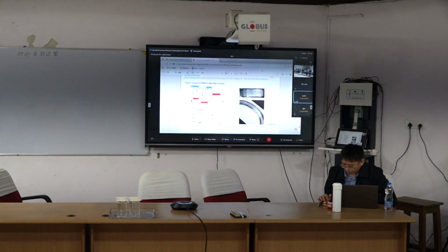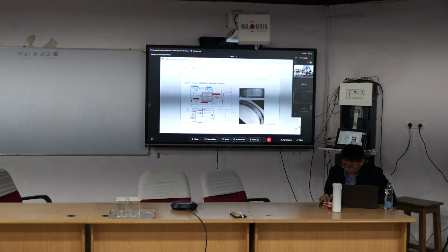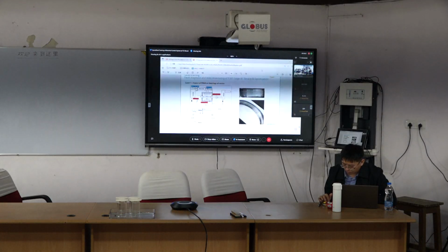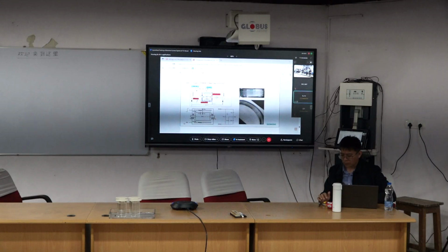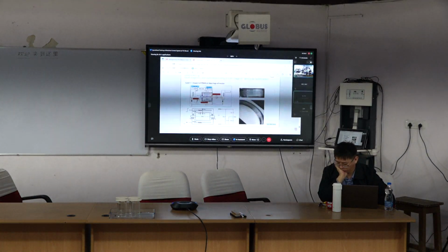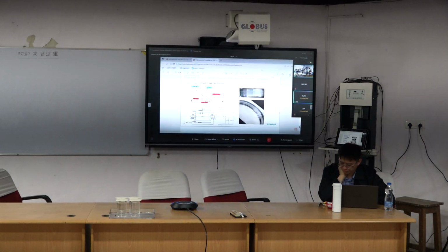In the same way, the motor cable capacitance changes polarity with every switching edge at the inverter output. The polarity of the capacitance CWH, this one, between the winding and housing, is also reversed with every switching edge.